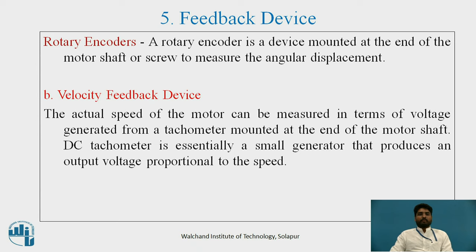A rotary encoder is a device mounted at the end of the motor shaft or screw to measure angular displacement. The second type of feedback is the velocity feedback device. The actual speed of the motor is measured in terms of voltage generated from a tachometer mounted at the end of the motor shaft. A DC tachometer is essentially a small generator that produces an output voltage proportional to the speed.